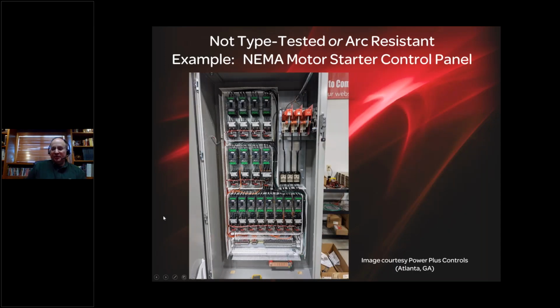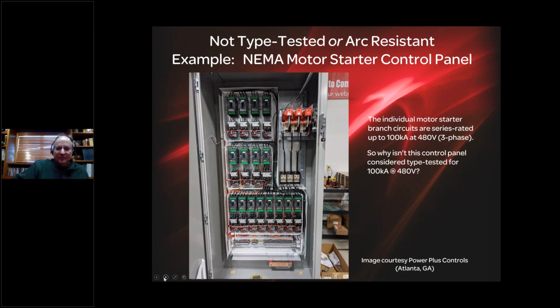So this is a picture. This is actually one of Mr. McClellan's panels with Power Plus controls. Was built just within the last 60 days. So the NEMA starters in this control panel, the individual motor starter branch circuits, are series rated up to 100 kA. So there is a short circuit rating on the components themselves.